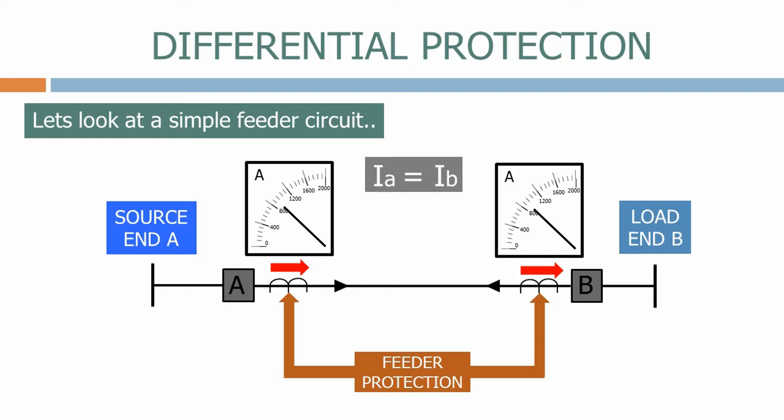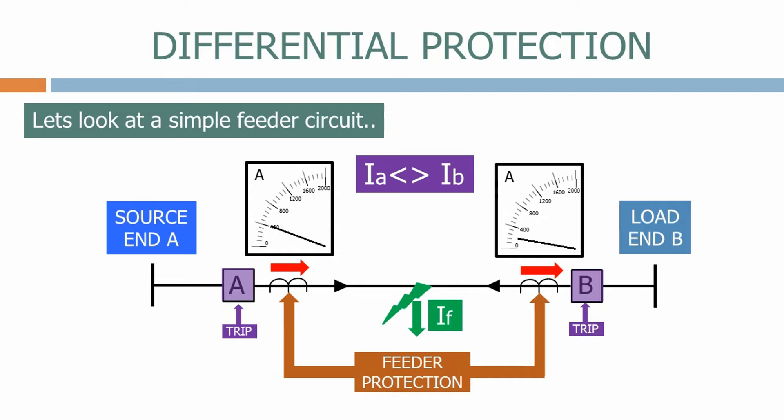Let's now apply a fault on the feeder. The current from the source at End A now increases substantially to feed the fault. The current at End B remains the same as it's still just feeding the loads connected to End B. There is now a large difference between the currents at ends A and B. The feeder protection immediately detects this condition and trips both circuit breakers, removing the fault from the electrical system.